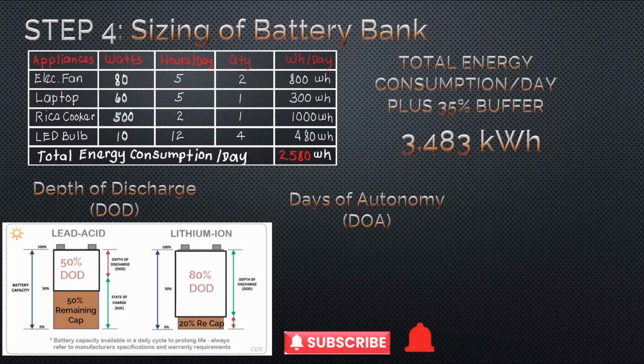For example, I will apply 2 days autonomy. Ibig sabihin, kung yung 1 day autonomy needs only 5 battery na 100 ampere hour each, so pag sinabing 2 days autonomy, you need another 5 battery na 100 ampere hour each. So the battery needed is 10 batteries na 100 ampere hour each. Pag sinabing days of autonomy, ito yung capacity ng battery to supply the loads independently, that is without solar or grid, but also considering the battery bank are fully charged.